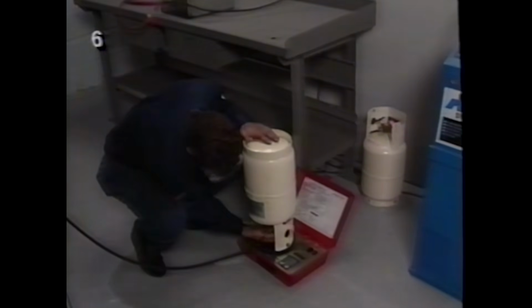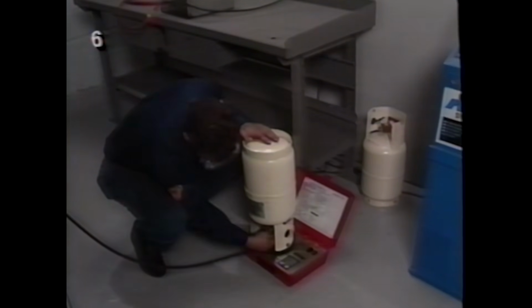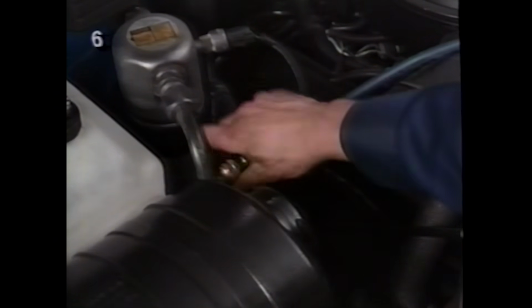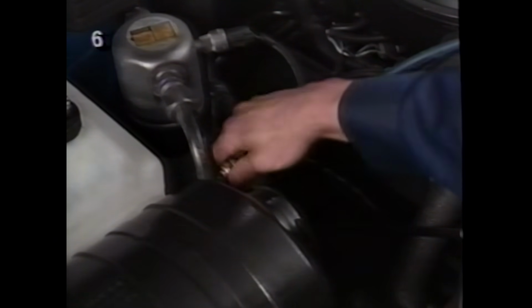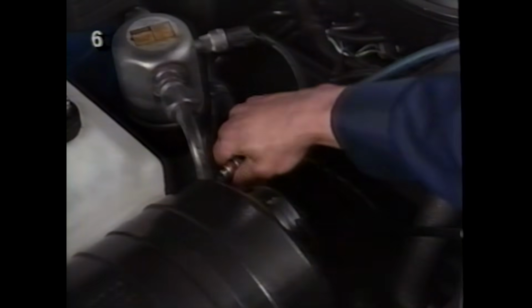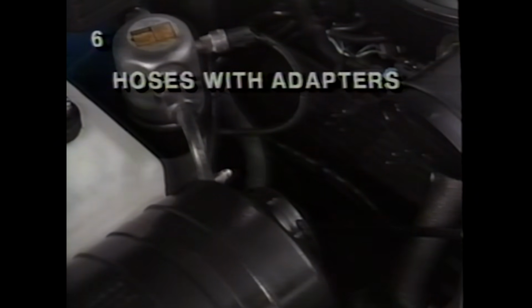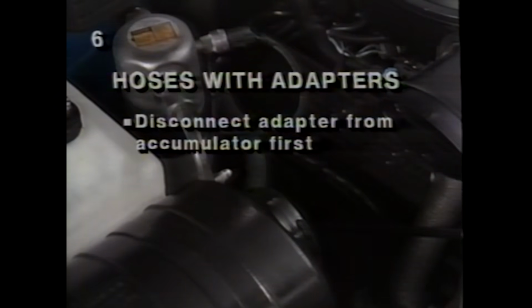When you've reached the spec, close the valve on the drum. Let the engine run another 30 seconds to clear the lines and gauges. Take the low side hose off the accumulator while the engine is still running. In this videotape, we are using quick seal hoses that do not require an adapter for charging the system. If you use hoses that require an adapter, be sure to disconnect the adapter from the accumulator first before disconnecting the adapter from the hose.